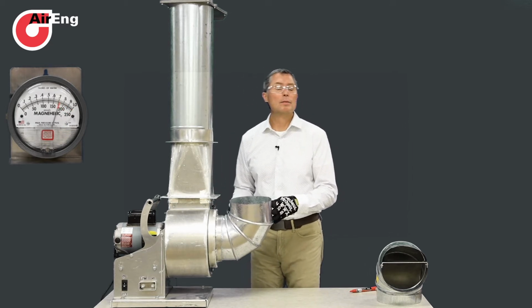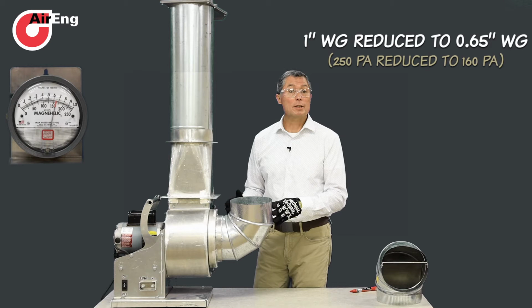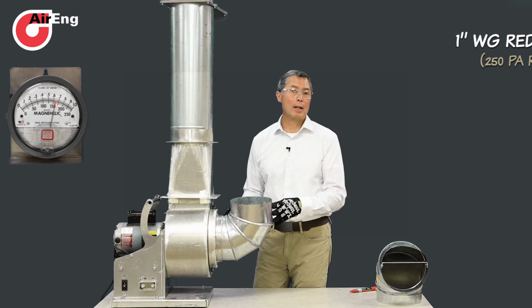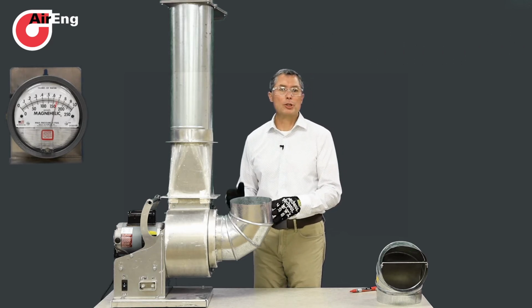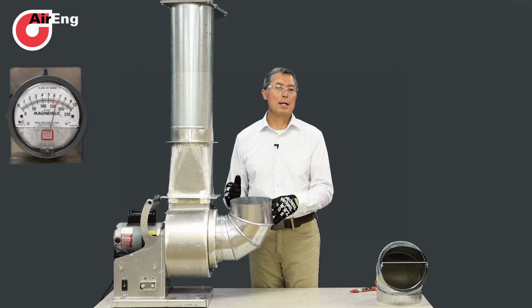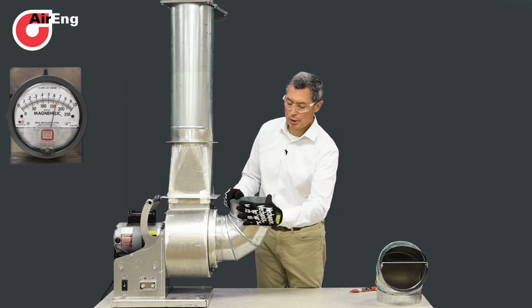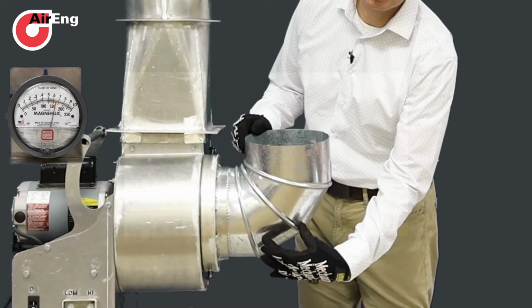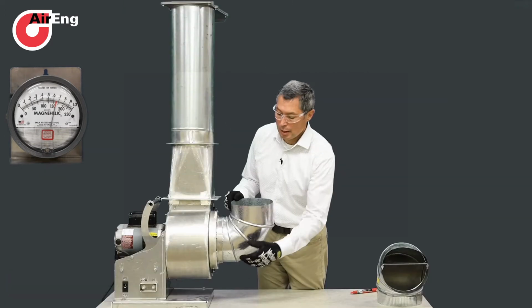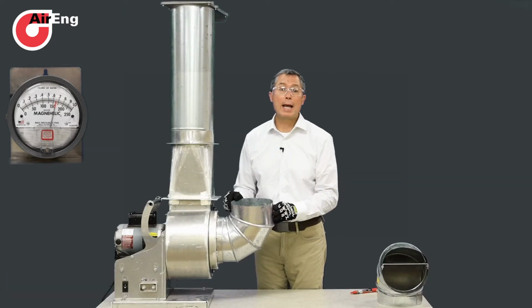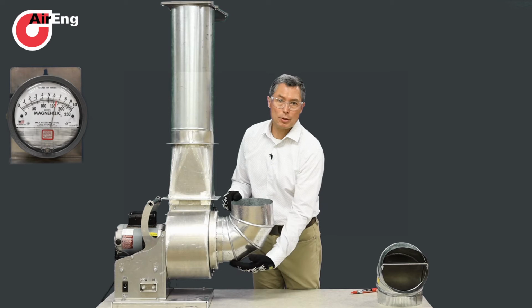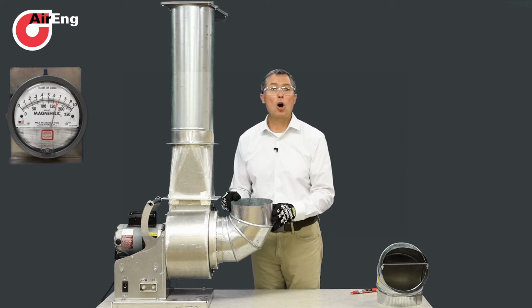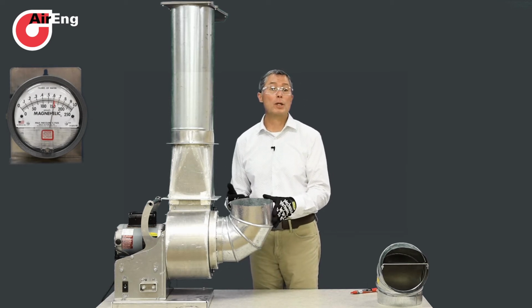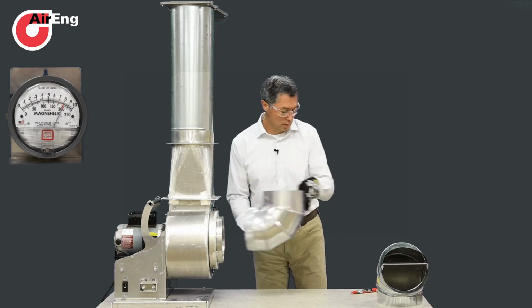Putting it on the fan, notice a couple of things. One, performance went down pretty substantially, which you can see on the meter. Secondly, you can hear the fan got louder. What we have to remember is air has mass, and that mass wants to go in a straight line. So it comes in uniformly, hits the bottom of the ductwork, and moves into the fan. The top portion of the wheel doesn't get any air - it's all going down to the bottom portion, and that's what's causing the turbulence, the additional noise, and the loss of performance.